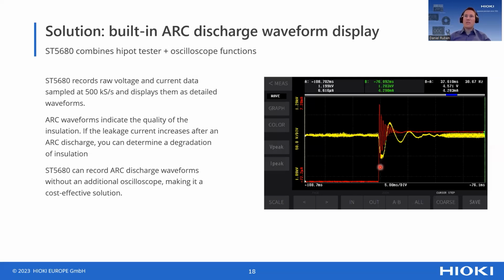So it can be the case that an arc is happening and the leakage current goes back to a smaller level, meaning there is no issue with the insulation inside, and therefore no reason for assuming there is any potential degradation happening. That means the ST5680, not only a safety tester but also with the oscilloscope function, gives the customer a much better way to analyze and to create the battery packs and modules during the production process, and afterwards, when they do the end of line test and an arc is happening inside.